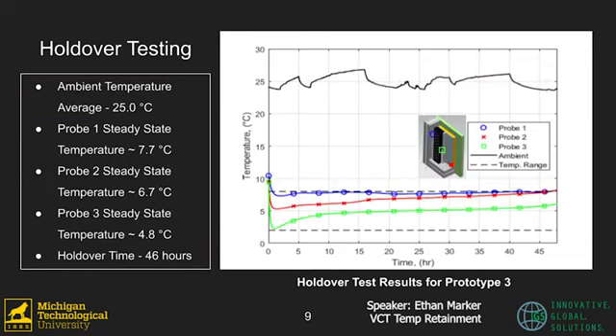This figure shows the results of the holdover test conducted on prototype 3. The ambient temperature of the testing room averaged 25 degrees Celsius. Probes 1, 2, and 3 held steady-state temperatures of 7.7, 6.7, and 4.8 degrees Celsius respectively. Probe 1 had the highest probe location in the container, and Probe 2 had the lowest probe location during testing.